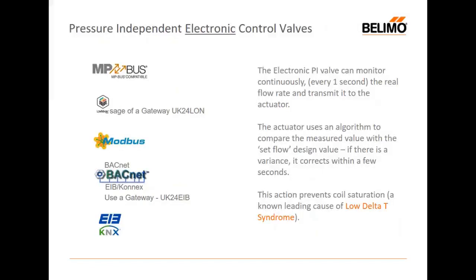Most electronic pressure independent valves can make use of one or all of these protocols. And when they are used in this way, we can send the design flow values to the BMS, so the BMS operator can see that the circuits are being satisfied or not. If there's a problem, then he can start to correct it. If there's a blocked strainer, he'll see the valve opening, but he won't see a corresponding increase in flow.